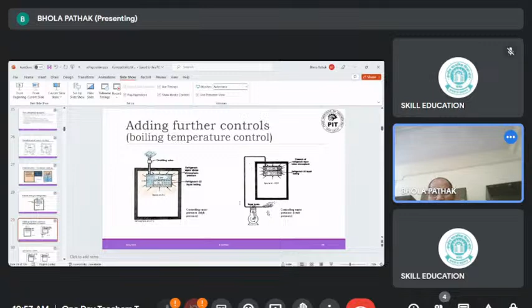What happens? One more control device has been incorporated here. A high pressure fluid we are supplying, and we are keeping a needle valve at the outlet of this high pressure supply zone, and we maintain a particular low pressure liquid in this chamber with the help of a float valve. This evaporates at some particular temperature, and that way also we can generate a particular temperature in this space, as this vapor is being picked up by the compressor and supplied to the next component.